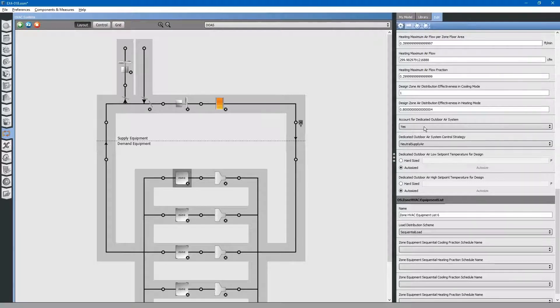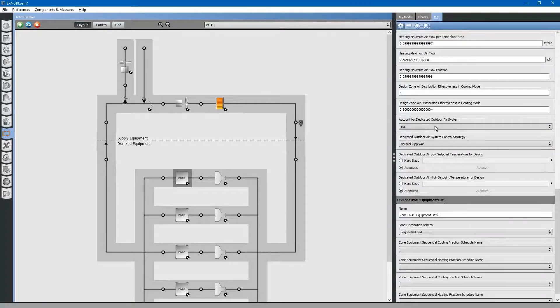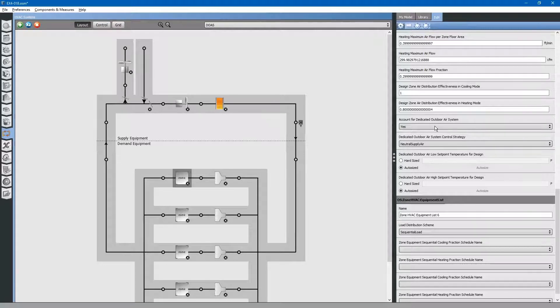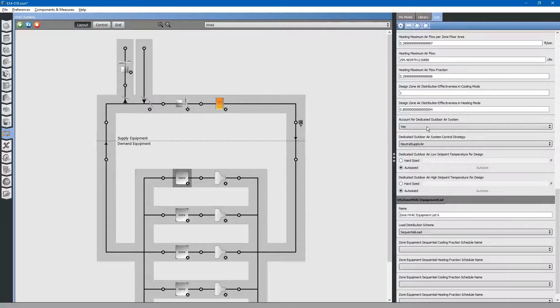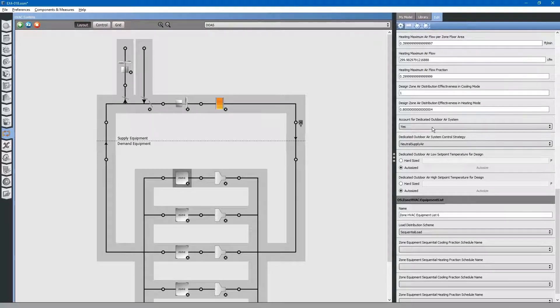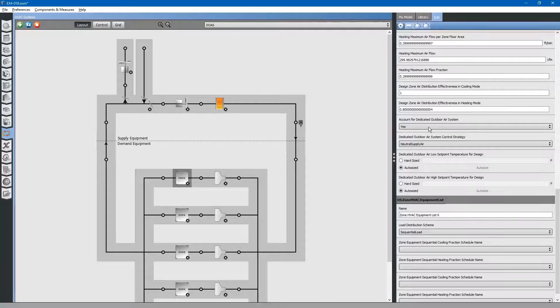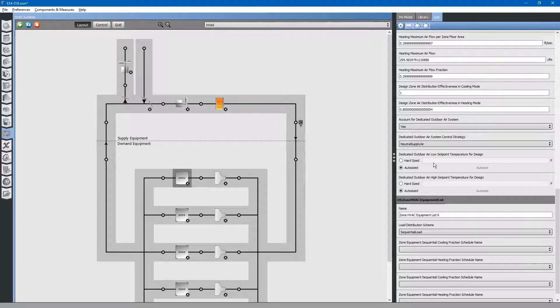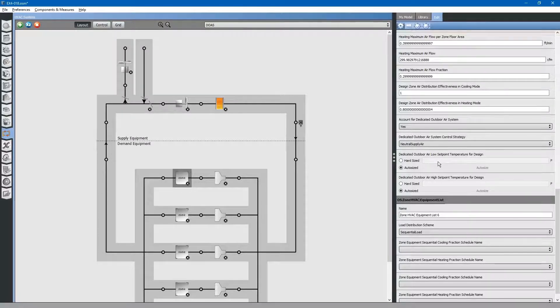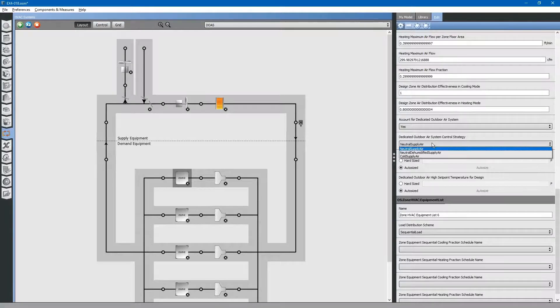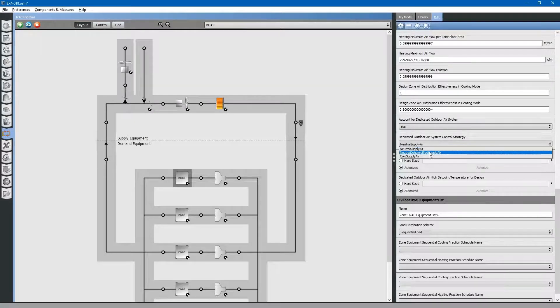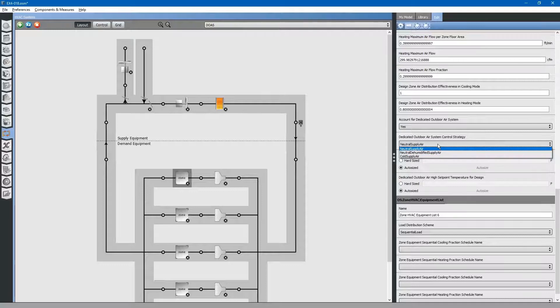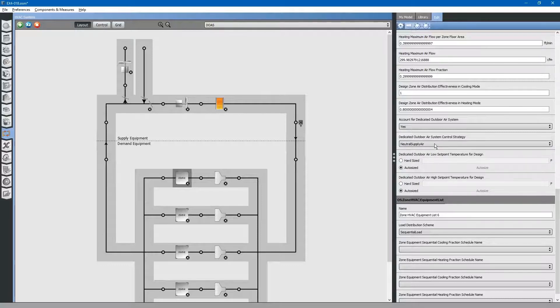This tells the program to add in the dedicated outdoor air system load effects on that zone before calculating equipment sizes at the zone level. For control strategy, we will just leave it at neutral supply air. If we leave these two at autosized, those would default to the default values for neutral supply air or whichever one you selected up here. You will have to go into the EnergyPlus documentation to find out what those values are.